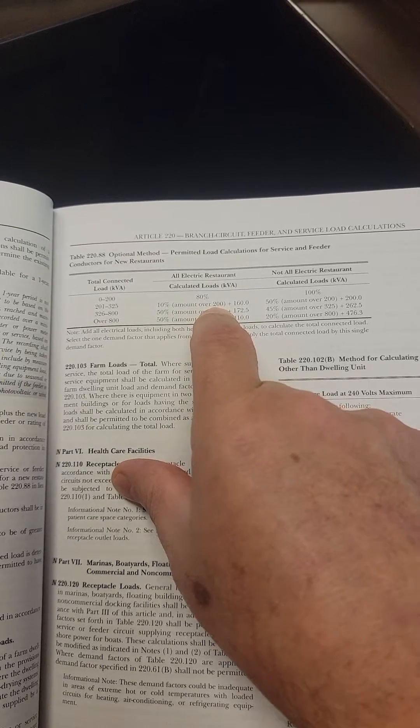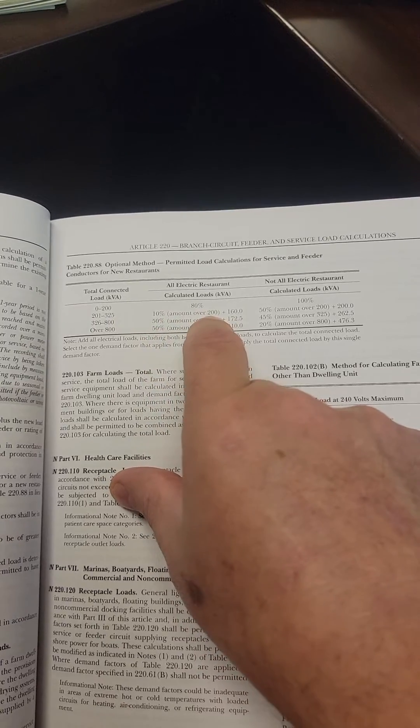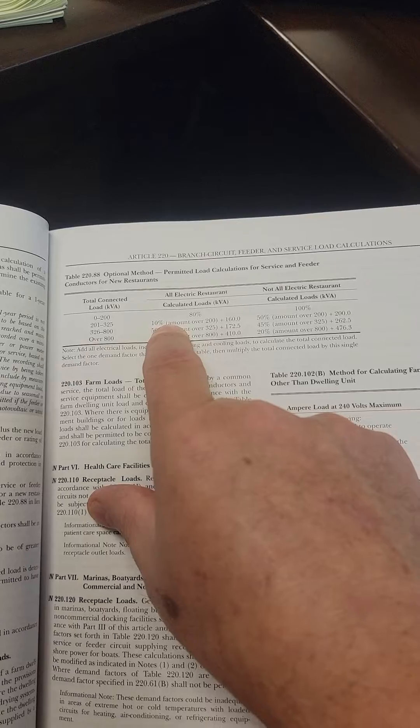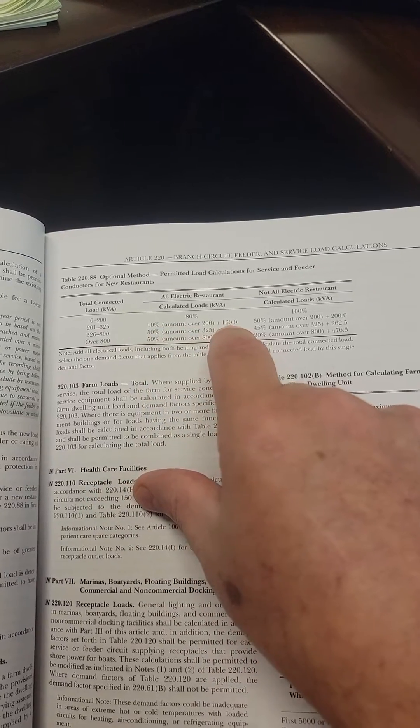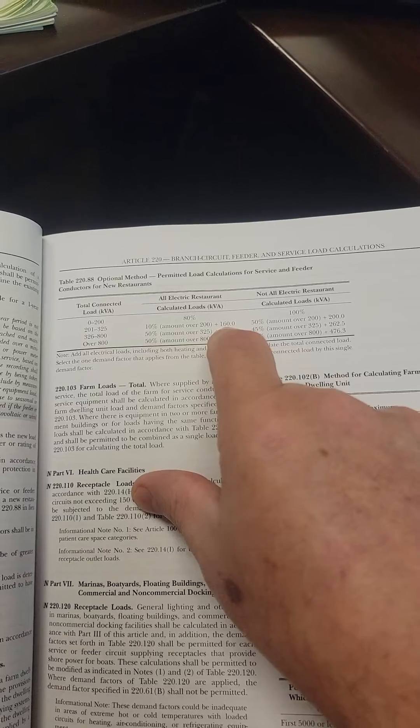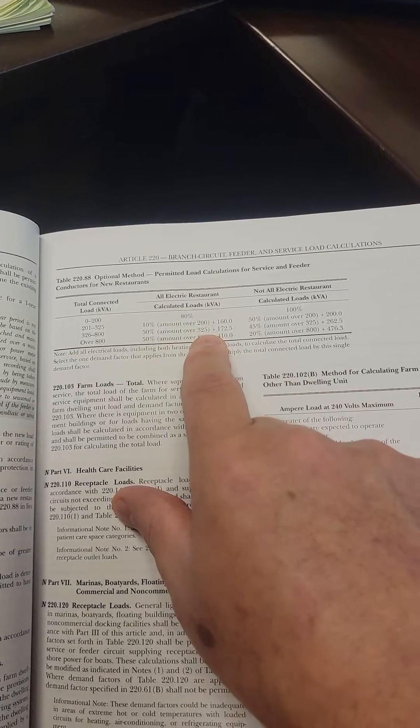You take 10% of that amount. So you'd use the 40 times 10%, and that is four. So that'd be 4 kVA plus 160. So it would be 164 kVA is the calculated load, and that's the answer to the exam question.